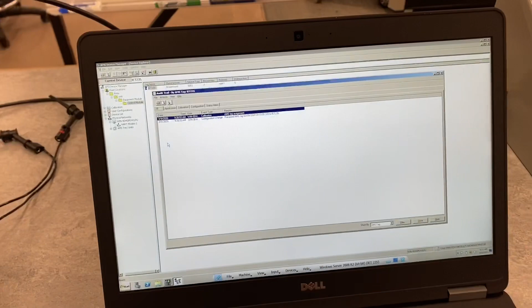The next thing we need to do is pair our Trex communicator with our AMS database. Once the two devices are paired, we can use this communicator when our transmitter is offline from the AMS database, to configure, make changes, and do calibrations on our transmitter.